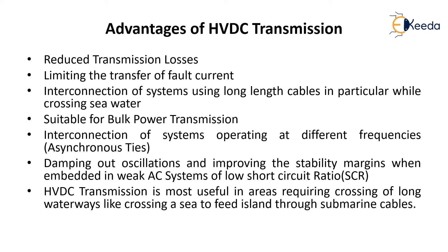The next important advantage is limiting the transfer of fault current, which is possible only in HVDC transmission — it is not possible in HVAC. Third, HVDC enables the interconnection of systems using long cable links, particularly when crossing sea water. When crossing sea water, systems can be interconnected using HVDC. This is not possible with HVAC because beyond 100 km reactive power loss occurs and reactive power compensation is required, making HVAC unsuitable for such underwater interconnections.